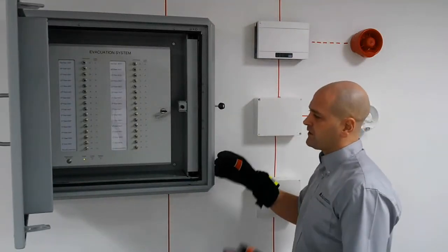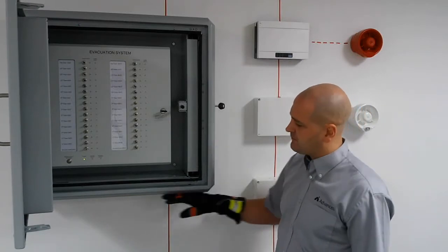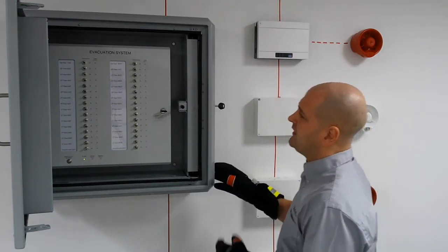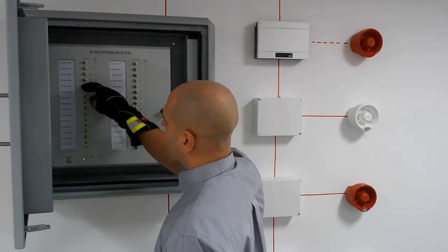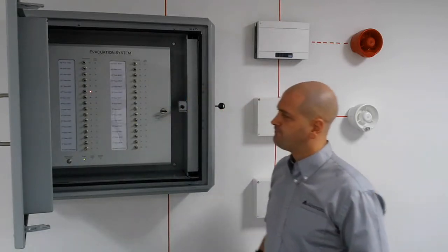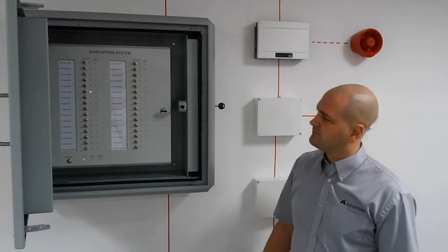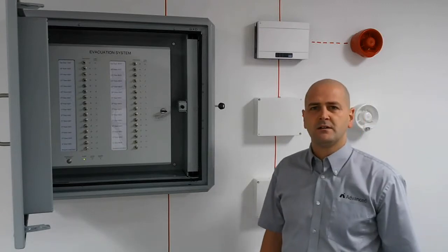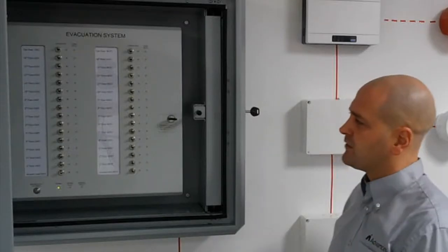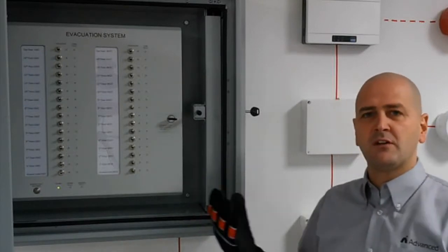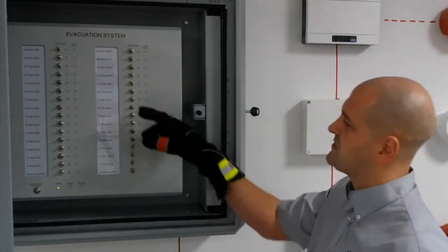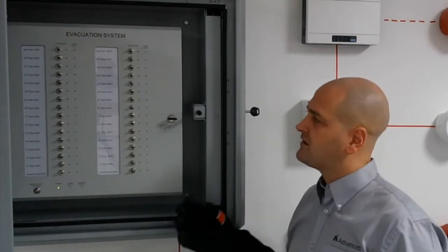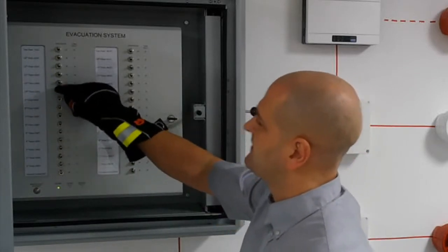They put in their key, turn the box, spring board in, so it will push the door open. And the fire and rescue service, you can see typically 1.4 meters is the minimum, which is the height we have here. And they should be able to safely evacuate a floor of origin. So they can turn on a floor, and they can deactivate an evacuation alert area. So the toggle switches are designed for use with the firefighter's glove. The switches are suitably spaced, and we can evacuate any floor that we see fit for purpose. So turn on the 10th floor again.